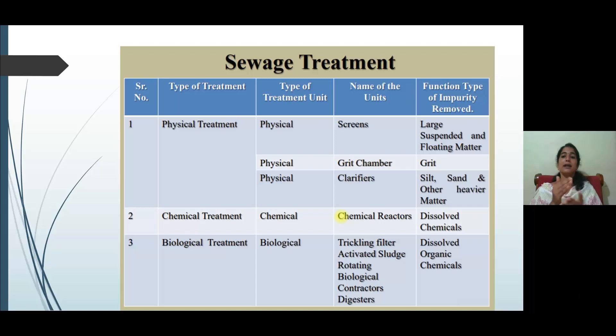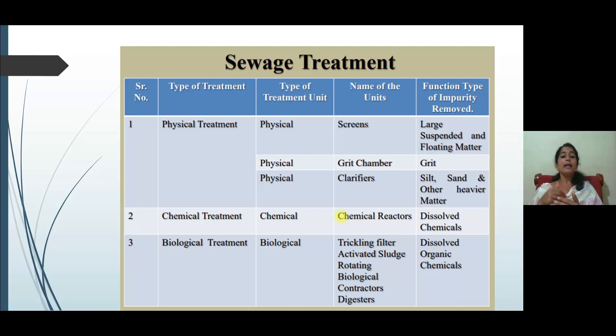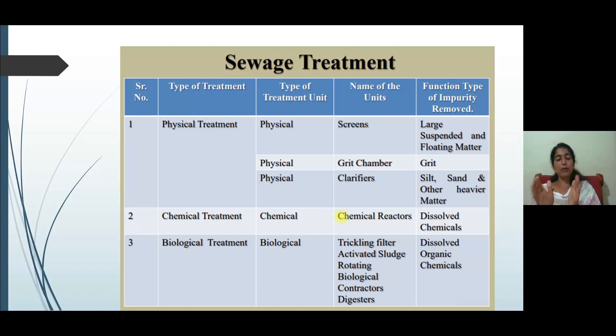In screens, large suspended solids and floating matter will be removed. In the grit chamber, grit particles — that is particles with a specific gravity ranging from 2 to 2.65 — will get removed. In clarifiers, silt, sand, and other heavier matter will get removed. In chemical treatment, chemical reactors are used to remove dissolved chemicals — this is a most important and somewhat difficult part of wastewater treatment. In biological treatment, methods such as trickling filters, activated sludge process, rotating biological contactors, and sludge digesters are used, by which dissolved organic chemicals can be removed from the wastewater.